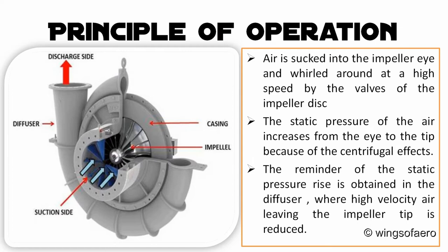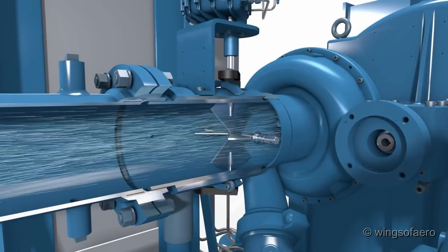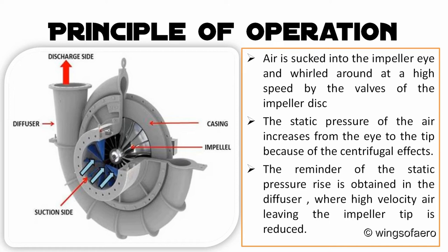In the principle of operation, air is sucked into the impeller eye through an accelerating nozzle and whirled around at high speed by the vanes on the impeller disc. At any point in the impeller, the flow experiences a centrifugal acceleration due to a pressure head. Hence, the static pressure of the air increases from the eye to the tip of the impeller.